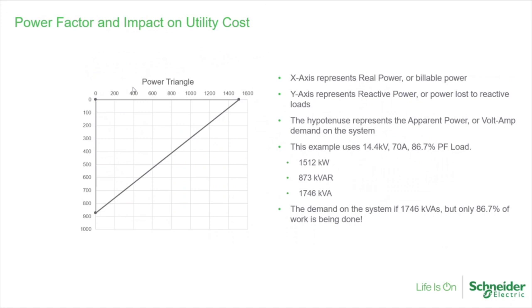For the example I was using, it was 120 volts, 3.5 amps secondary, but as a primary example, a 14.4 kV line, 70 amps primary, and an 86.7% power factor. So in this example, we have about 1.5 megawatts, 873 kVAR, and 1,746 kVA. What I'm trying to illustrate is if you have a customer with a low power factor, you're only billing them for 1,512 kilowatts per hour if they're running consistently. But their demand on the system is actually 1,746. So that's a couple hundred kilowatts that isn't being billed, but is still a demand on your system. Your generators are having to produce more to deliver the same amount of work.